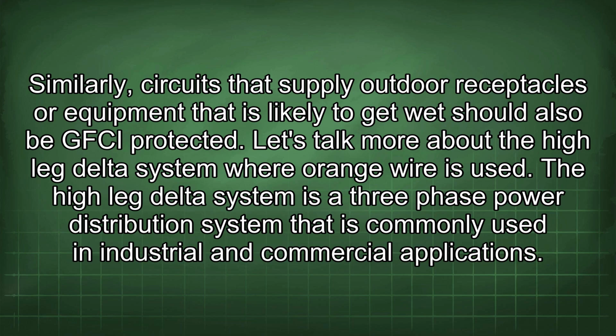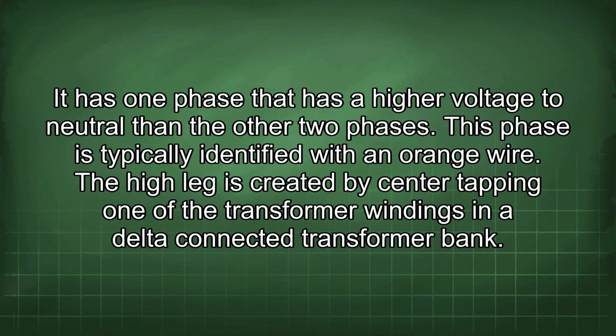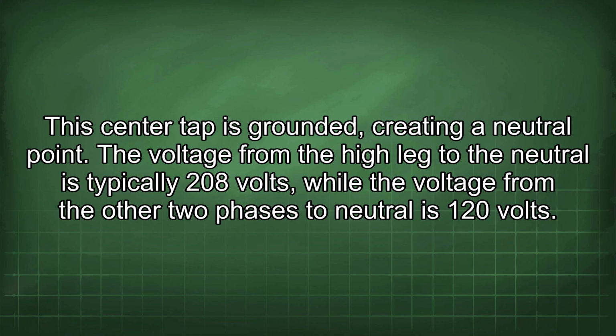Let's talk more about the high-leg delta system where orange wire is used. The high-leg delta system is a three-phase power distribution system that is commonly used in industrial and commercial applications. It has one phase that has a higher voltage to neutral than the other two phases. This phase is typically identified with an orange wire. The high leg is created by center tapping one of the transformer windings in a delta-connected transformer bank. This center tap is grounded, creating a neutral point. The voltage from the high leg to the neutral is typically 208 volts, while the voltage from the other two phases to neutral is 120 volts.